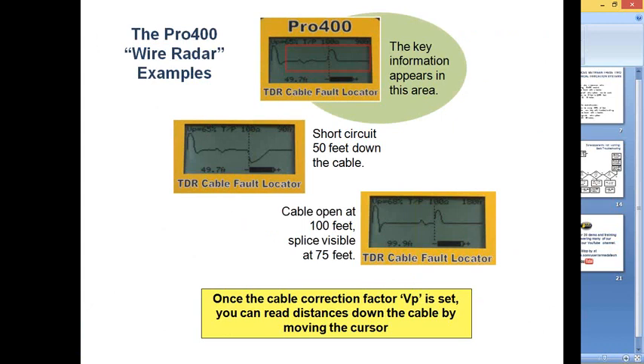A couple more illustrations of signals, transmissions that we did during testing and training. The blip is like an old-fashioned radar or sonar system. You send a pulse out from the left and you get a blip coming off to the right. You slide your cursor over and read the distance. If you set the correction factor on the cable correctly, you can find this stuff. So that's another tool that's available, and it may be necessary sometimes to help find the valve boxes.